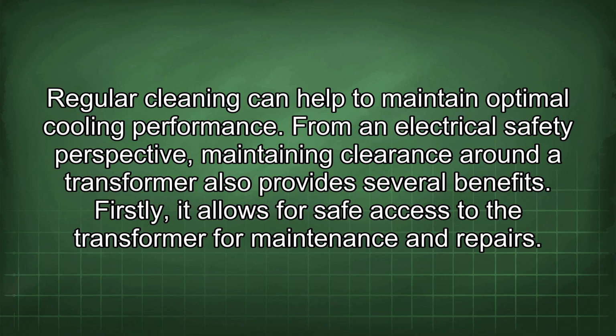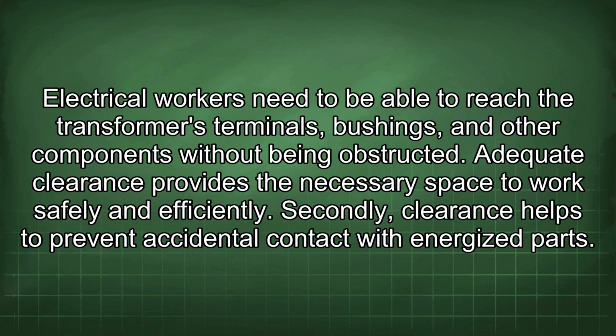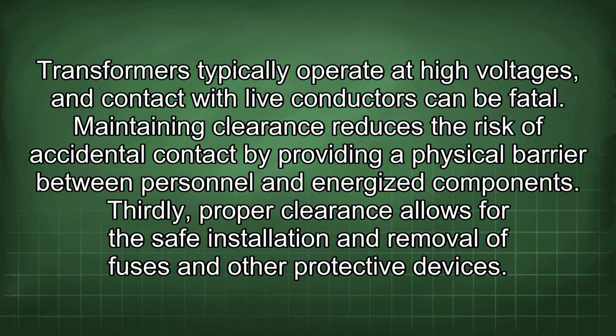From an electrical safety perspective, maintaining clearance around a transformer also provides several benefits. Firstly, it allows for safe access to the transformer for maintenance and repairs. Electrical workers need to be able to reach the transformer's terminals, bushings, and other components without being obstructed. Adequate clearance provides the necessary space to work safely and efficiently. Secondly, clearance helps to prevent accidental contact with energized parts. Transformers typically operate at high voltages, and contact with live conductors can be fatal. Maintaining clearance reduces the risk of accidental contact by providing a physical barrier between personnel and energized components.